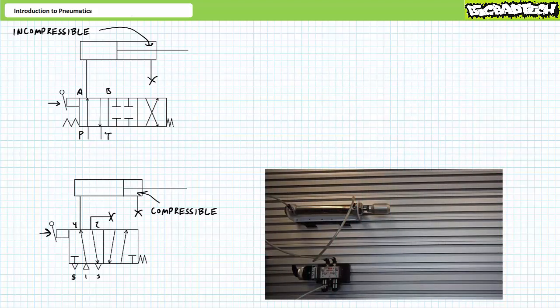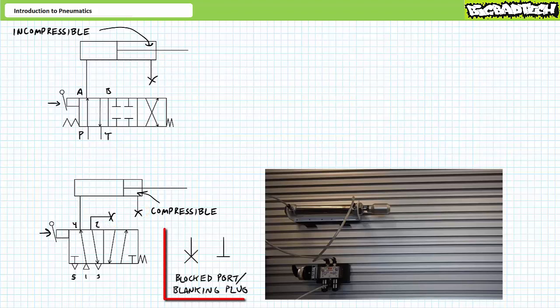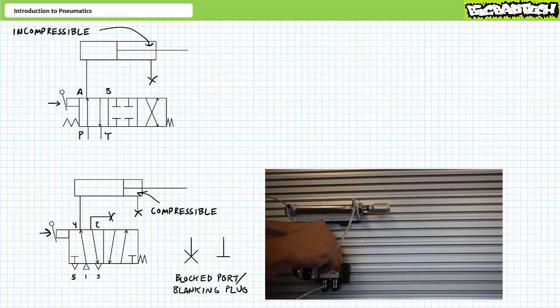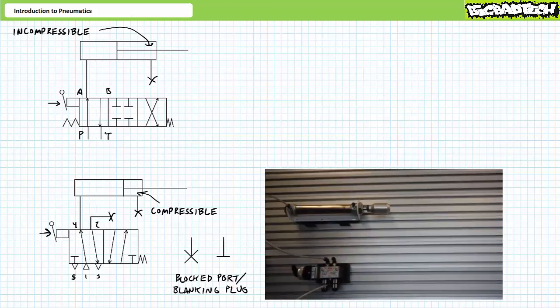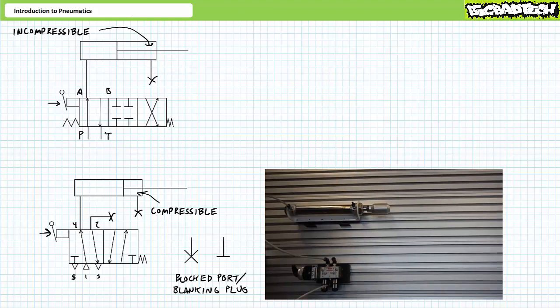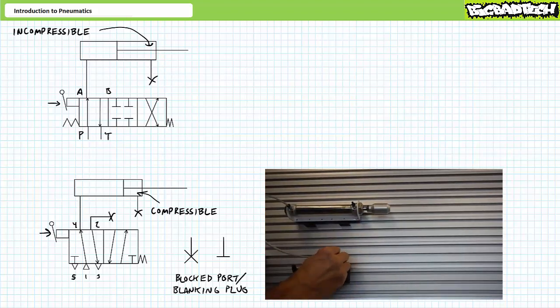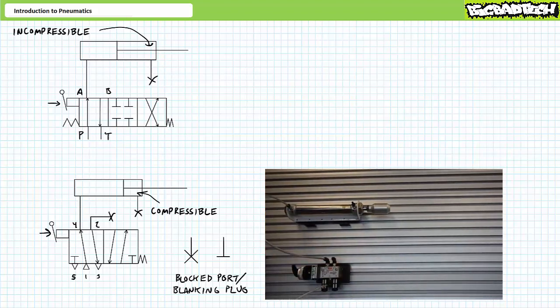Not so in a pneumatic system. Consider a double-acting pneumatic cylinder with a blocked rod end port. Schematically, blanking plugs are represented as X's or sometimes T's. If we shut off the incoming air and place a blanking plug on both the rod end port and the valve, turn the system back on and shift the valve to the extension position, we'll find the cylinder continues to extend, albeit with less force and speed as the air in the blocked rod end is compressed.